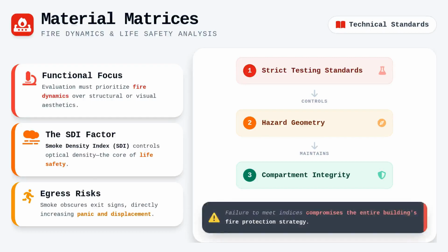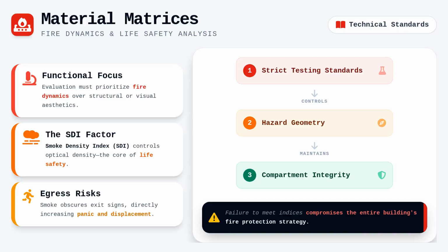Remember that fire codes are built upon the assumption that the integrity of the compartment is maintained by the materials forming its interior surfaces. When those surfaces fail to meet their designated indices, the entire fire protection strategy for the building becomes compromised. Focus your study on how these indices are derived and the physical conditions they represent in the field.